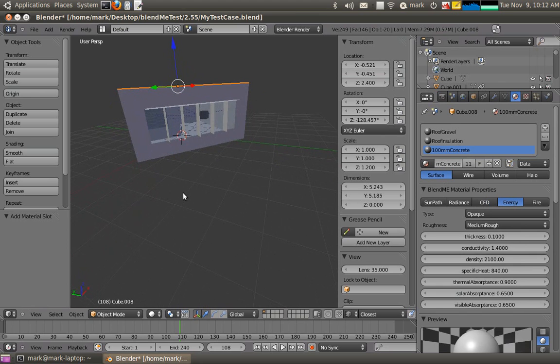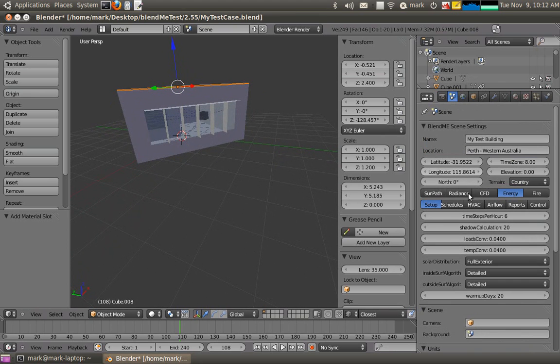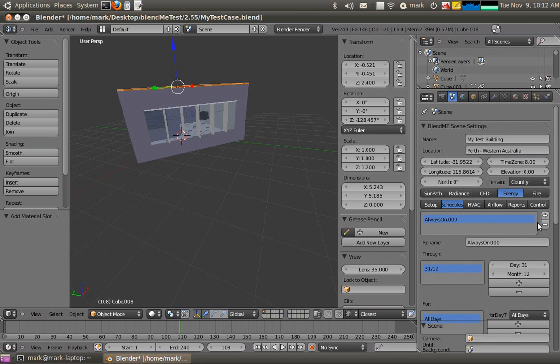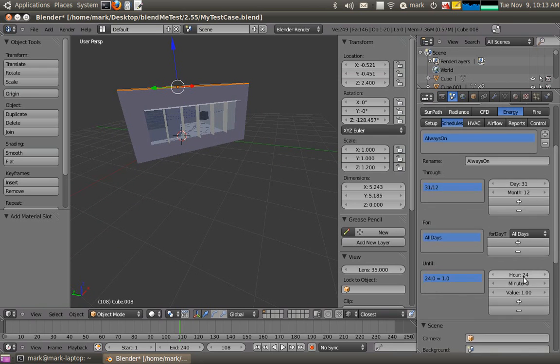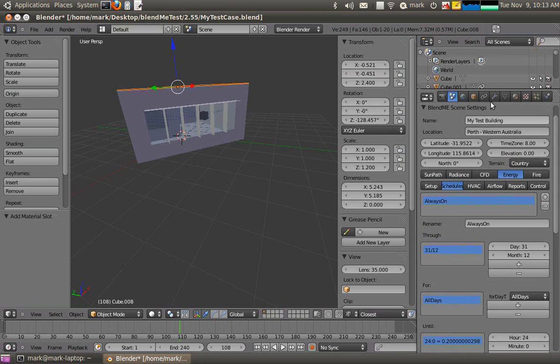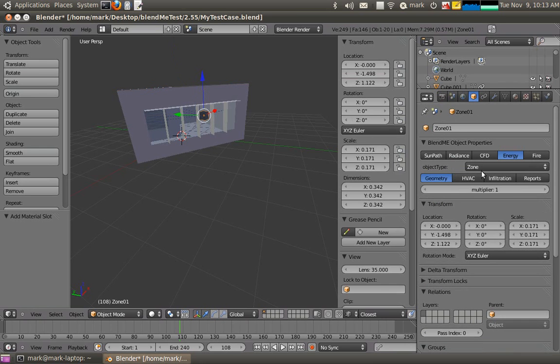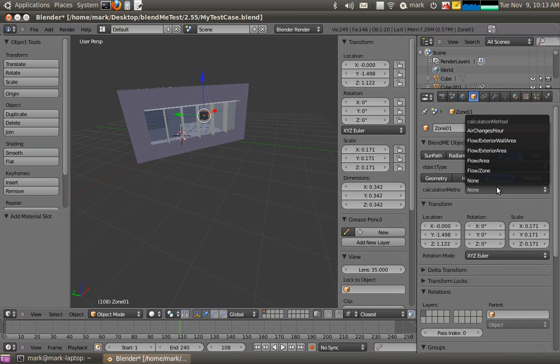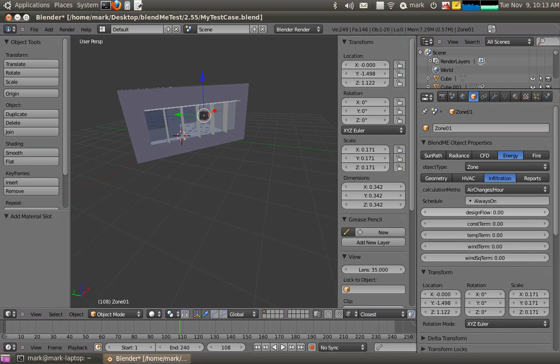Now I still haven't set my infiltration. So remember in order to add infiltration I needed my always on schedule. It could be called anything, but I'll just call it always on so there's always infiltration there. Value of 0.2. If I go back to the objects and select my zone, I can have air changes per hour using the always on schedule. Design flow rate of 0.2.